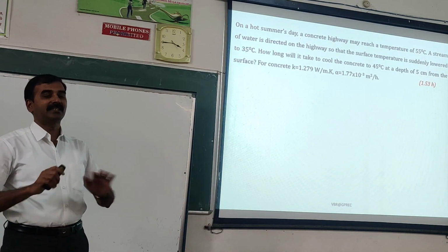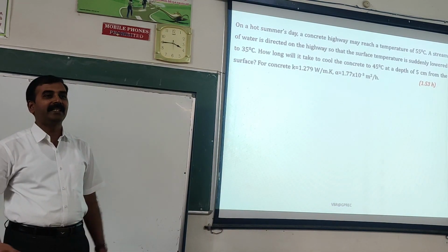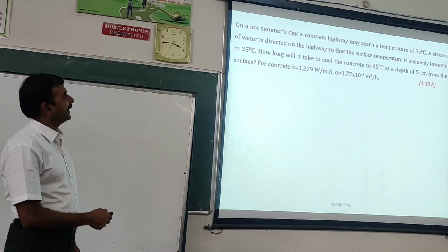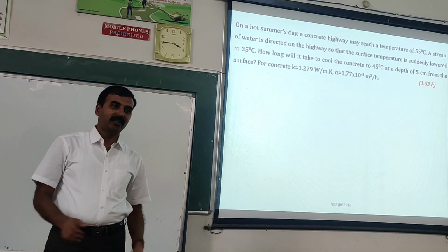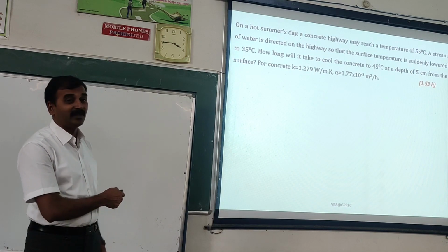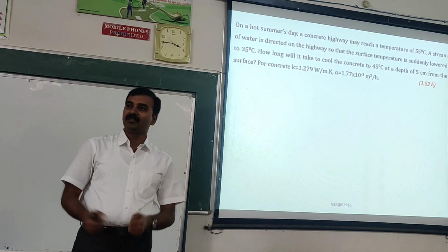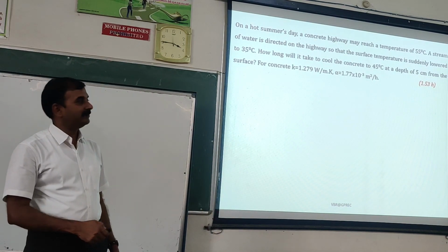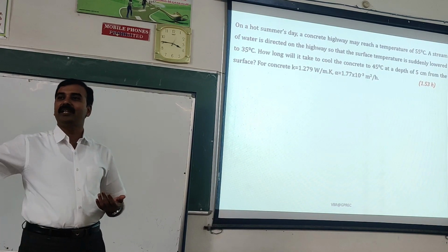But here the condition is that the surface is lowered to that. Then because of that, what's the effect? How is the heat being transferred within the body? That is the effect. So now, how long will it take to cool the concrete? Now suppose you are constantly pouring this. You haven't stopped pouring the water. So therefore the surface is now fixed at this temperature. You are not allowing it to deviate. You are continuously wetting the surface with water. You have not just poured it and then put it off. It's continuously on. So under that condition, naturally the body gets cooled slowly. That cooling effect penetrates gradually deep inside.